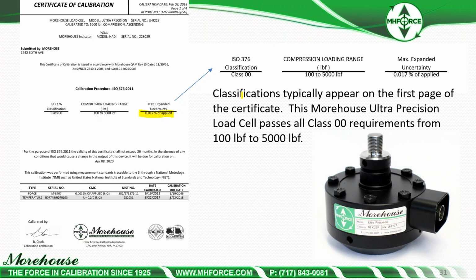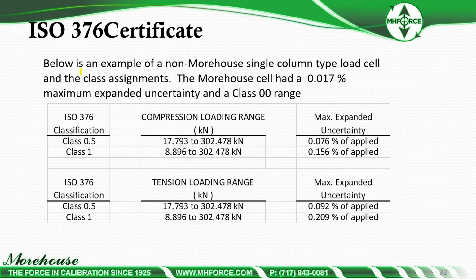So classifications typically appear on the first page of the certificate. The Morehouse Ultra Precision Load Cell passes class 00 requirements from 100 to 5,000 pounds, with 0.017% of applied right there. So if we go and use this cell, max uncertainty, the best we're going to be able to do is do a class half calibration with it, if we're using that max uncertainty. And then I have an example of a non-Morehouse cell. This is pretty typical, a cell sent into us for calibration. And I was trying to explain that range there.